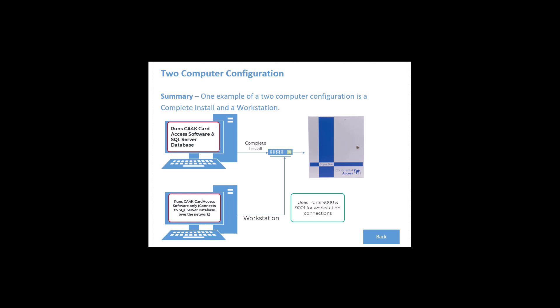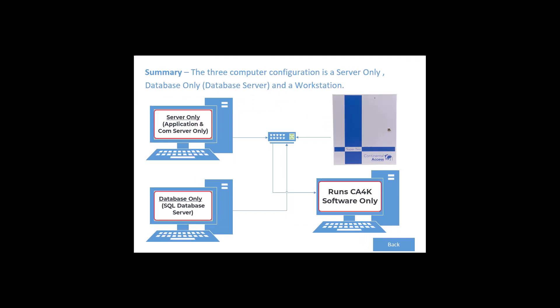The second configuration consists of a complete install and a workstation install, requiring a total of two computers. The third configuration consists of a server-only installation on the CA4K host, a database-only install, and a workstation install, requiring a total of three computers. The database-only installation is also called a database server, whose primary function is to have SQL installed on it along with the CA4K live and archived databases.